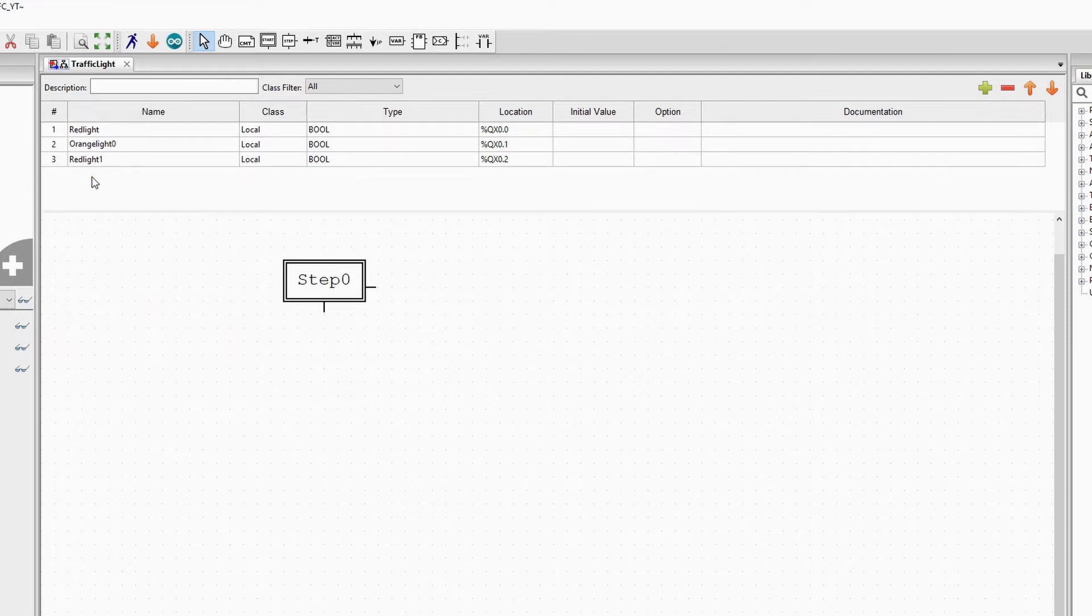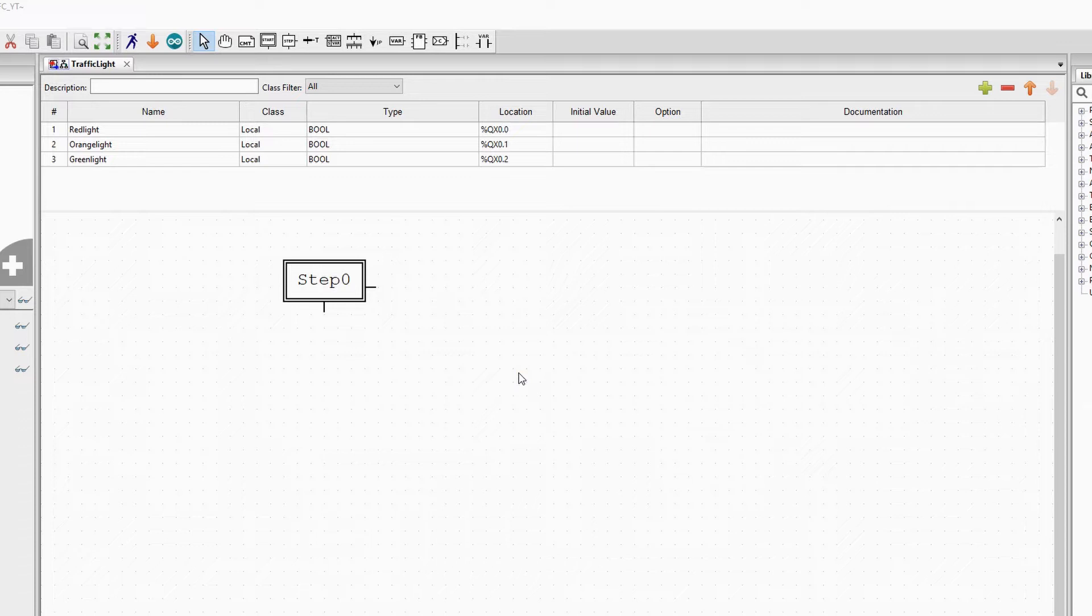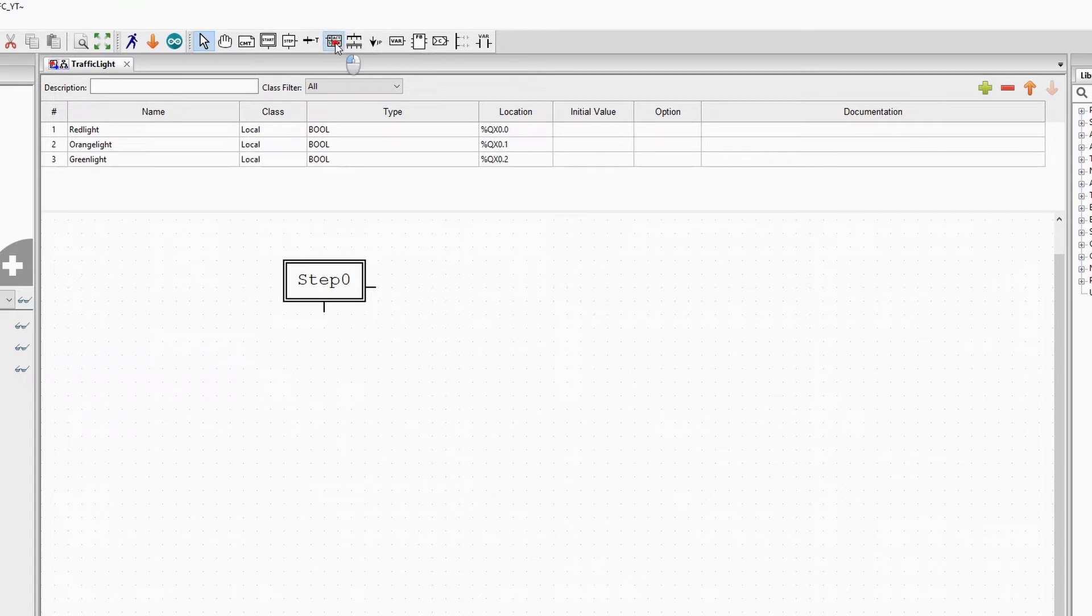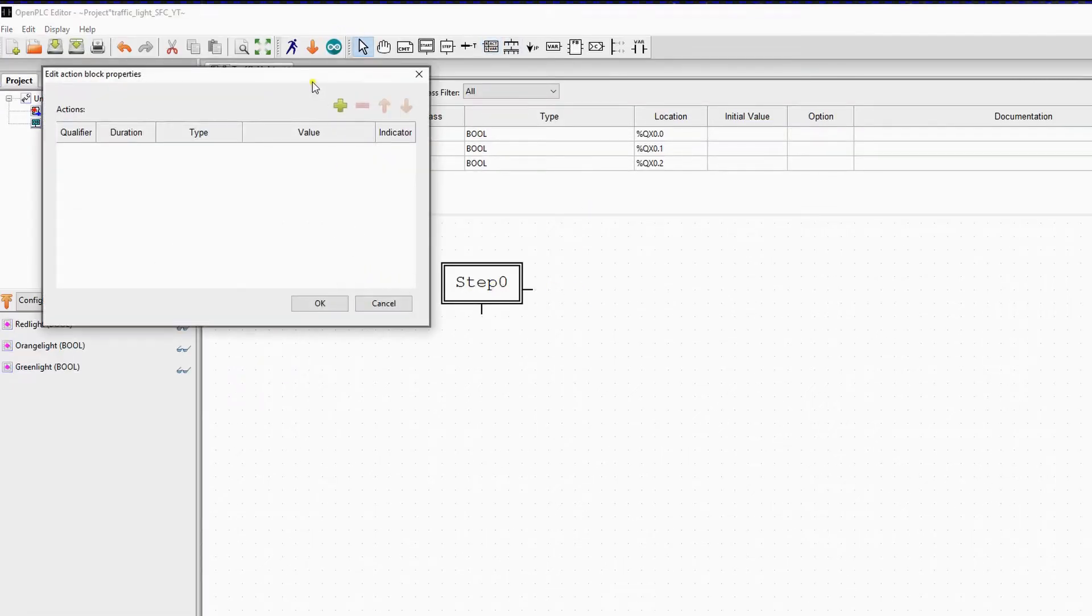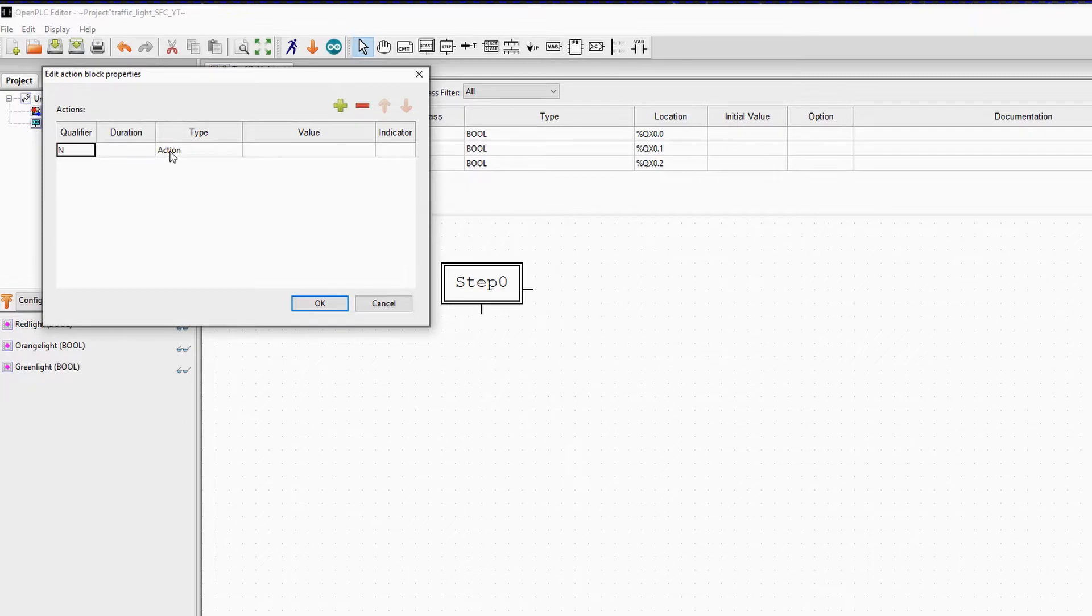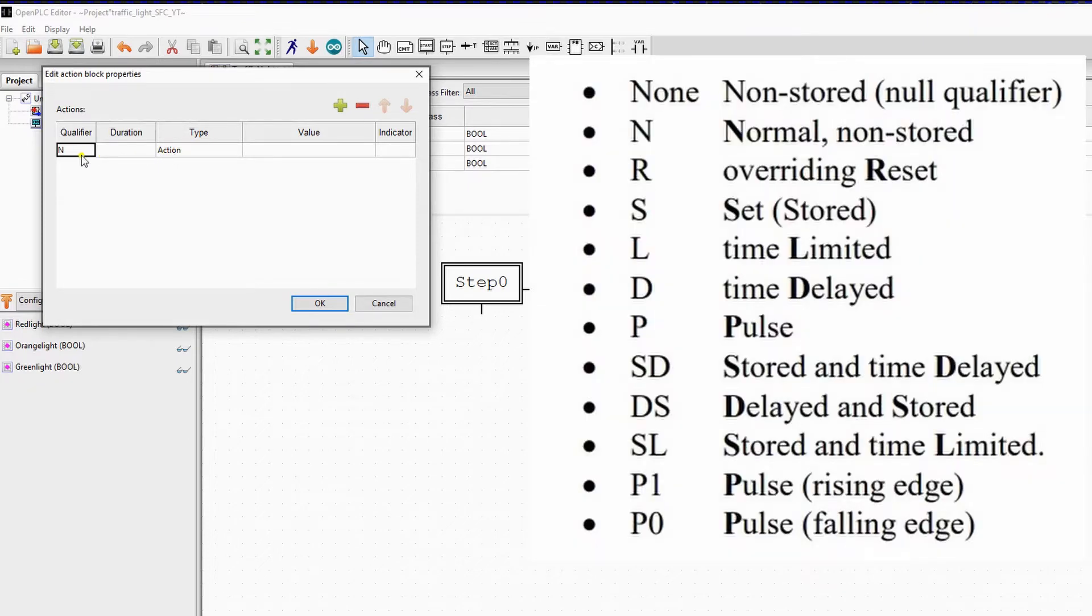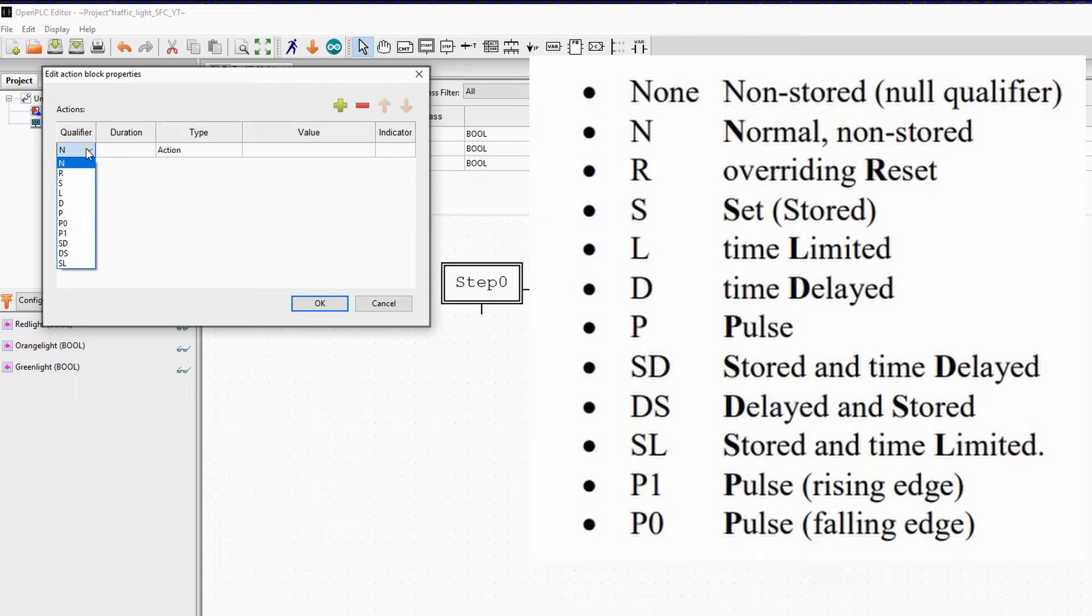Now we will add an action to the initial step. This will activate the red light. We will do this by selecting the action symbol in the toolbar and clicking in the work area. We will get this new popup and press on the plus button to add an action. First we have to choose a qualifier. You have many qualifiers, but the most intuitive and mostly used is the N qualifier. The N stands for normal non-stored.